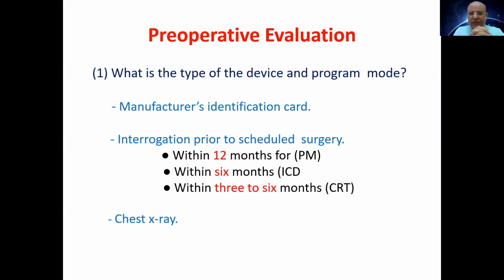Number 1, what is the type of the device and what is the programmed mode? You have to know the type of the device, either from the patient himself, a patient who came with a card, or a manufacturer card, or you contact his cardiologist. But sometimes you don't have this. So you need to know the device, what the program was, and so you know what the indication is. As I said, you have to know the indications.